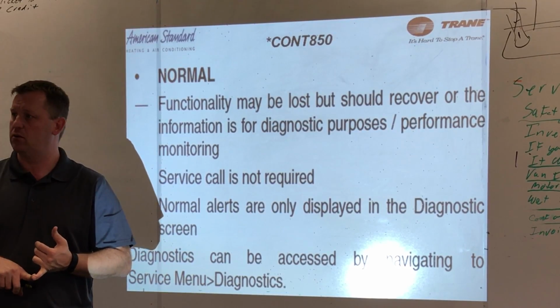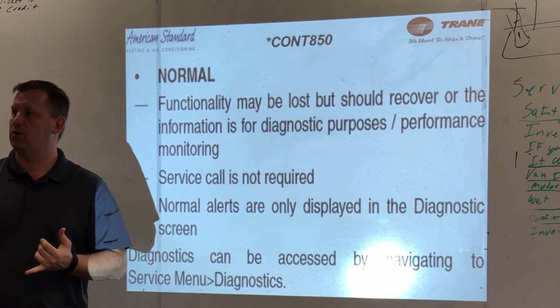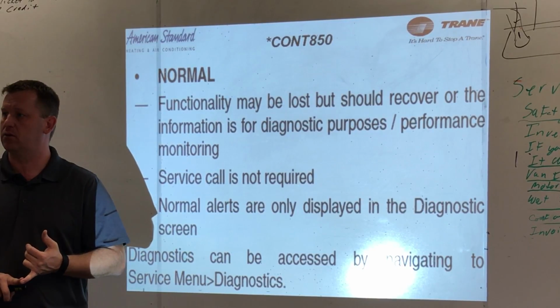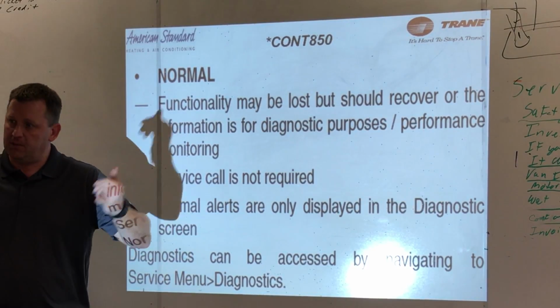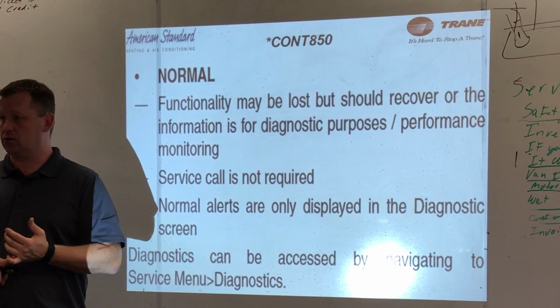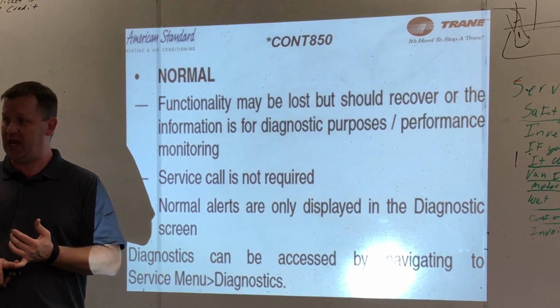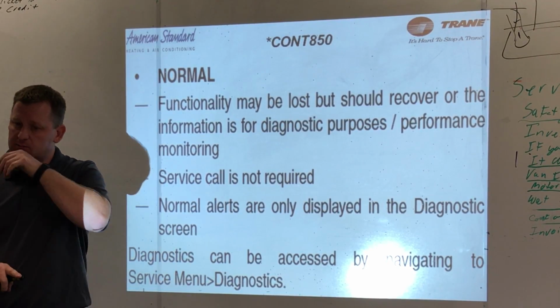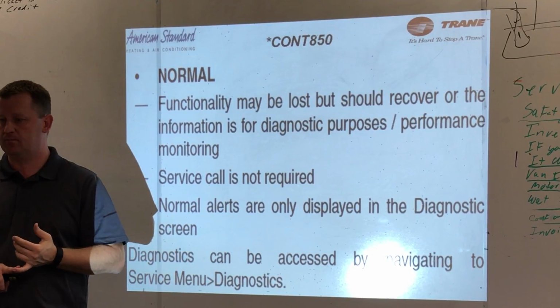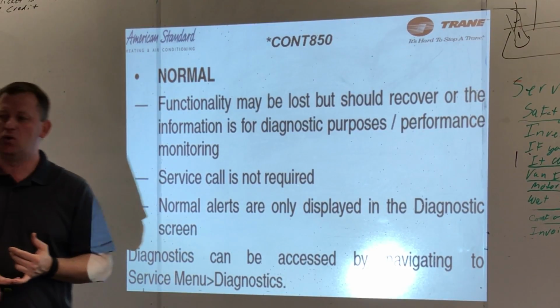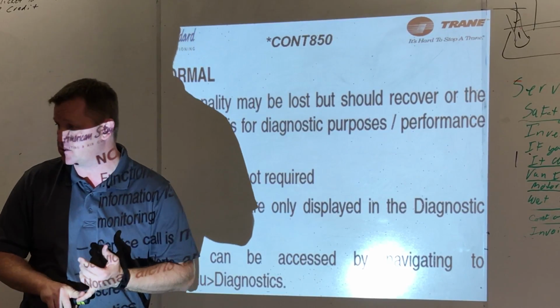I'm running into that with a machine right now. They wanna run it 65 degrees in the house and 50 degrees outside. You're gonna get frost protection alerts. It's gonna happen. After so many normal alerts, will it go into a major or critical? In most cases, no. On low suction pressure, yes. That's one. Okay.